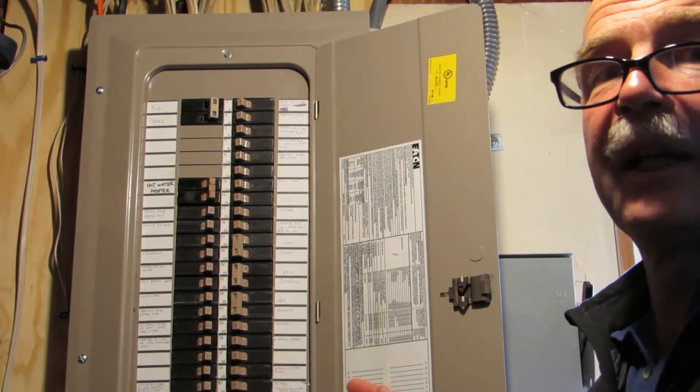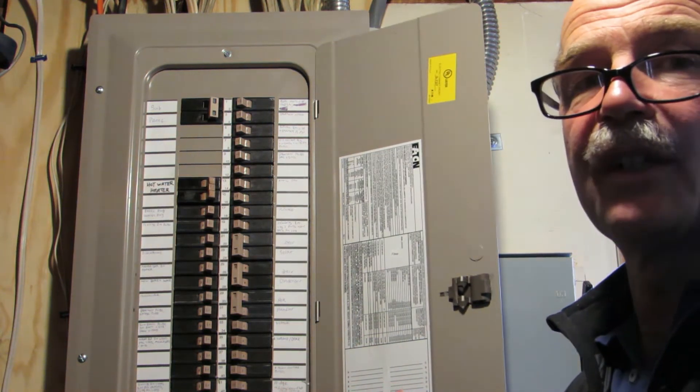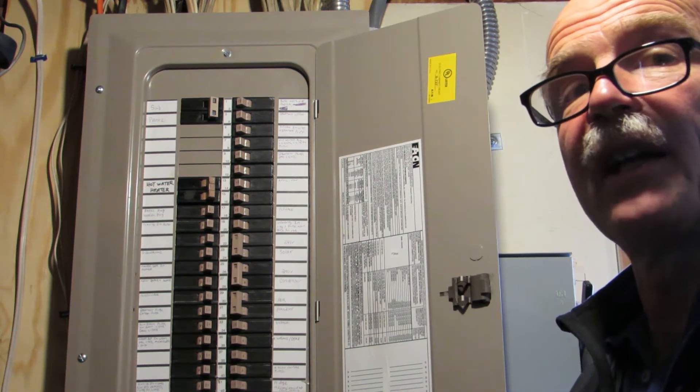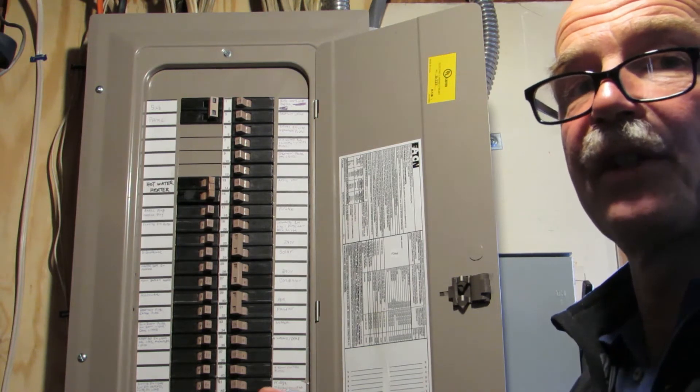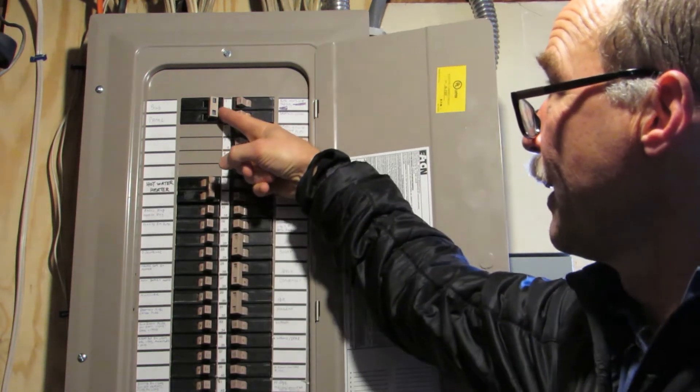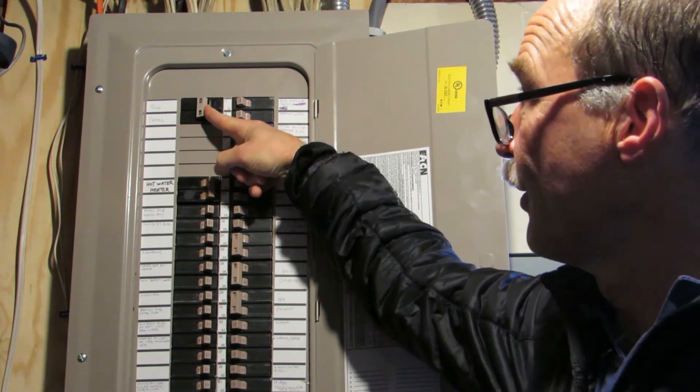Here we are at the main circuit breaker panel for the house, and we're going to install the charging station in the garage, and there's a sub-panel in the garage. So to be safe, we're going to turn off the electricity of the sub-panel. We're going to do that by just flipping this 100-amp breaker over like that.